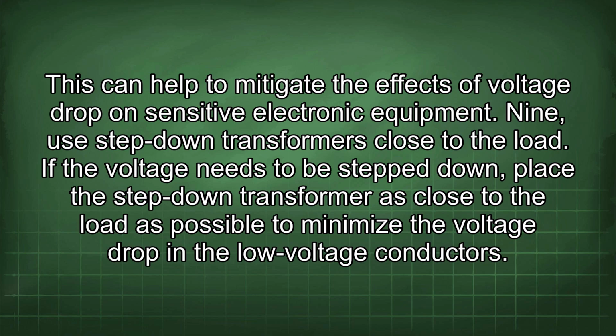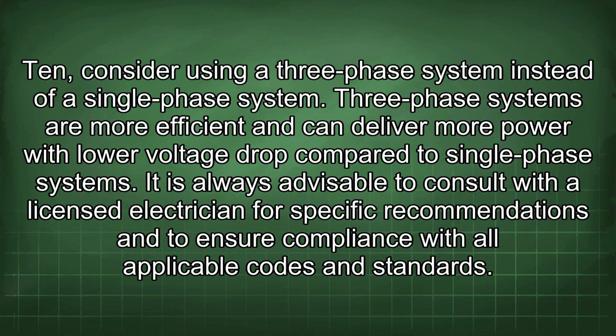9. Use step-down transformers close to the load. If the voltage needs to be stepped down, place the step-down transformer as close to the load as possible to minimize the voltage drop in the low-voltage conductors. 10. Consider using a three-phase system instead of a single-phase system. Three-phase systems are more efficient and can deliver more power with lower voltage drop compared to single-phase systems.